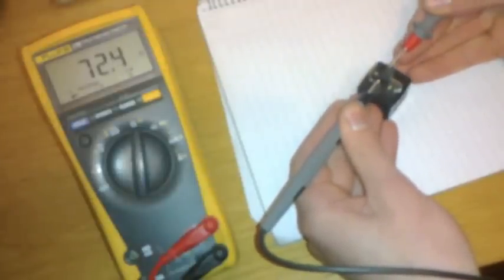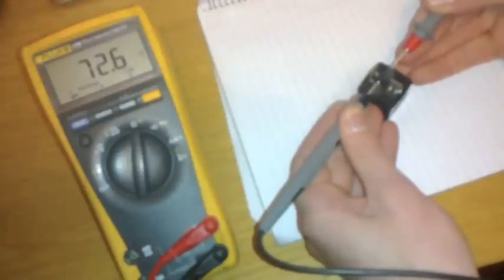So to test that the coil is still okay, using a multimeter set on the ohms range, we probe the two small terminals that are attached to the coil inside. Here we can see we get 72 ohms, which is a good reading meaning that there's still a good coil in there. There's no breaks in the wire that we can see.